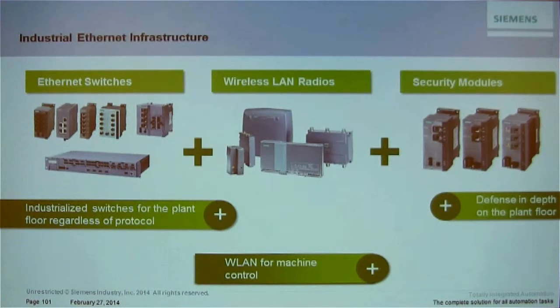And then if one of these devices does not seem to work as planned, guess what? All of these devices have these LEDs on them. Out of human nature, we look at these LEDs and say, hey, the LED is not blinking, the device might be bad. Well, fine, we wait for a new component to come in, swap it out. Again, that LED isn't working. Well, have you tried pulling up that patch cable? Have you tried looking at our connector, a little RJ45, which wiggles back and forth? Have you looked at the switch that's supporting these applications?